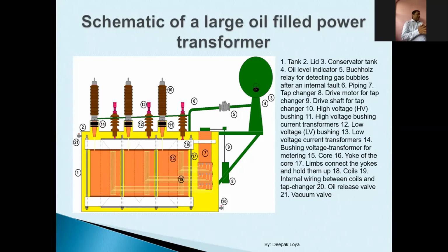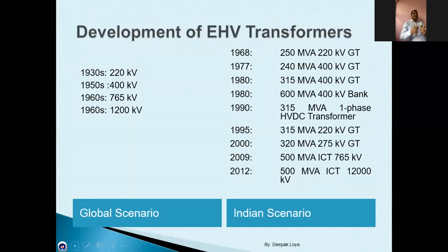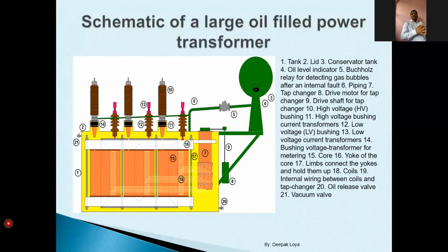In industry, both practices are being followed. There are hermetically sealed transformers which have better tank mechanical capacities and can handle higher pressures, or we use conservators. A conservator is a tank, an empty or half-filled tank, which is connected to a breather. The breather is literally breathing in or breathing out the air which is left over in the conservator. When my oil volume expands, the oil level in the conservator will increase and it will push the air out. When the oil is cooled, the volume will contract, so the volume in my conservator tank will come down. The remaining volume will be filled with air. From where will this air come? Again from the breather. So the transformer will breathe in. That's why the conservator is there.